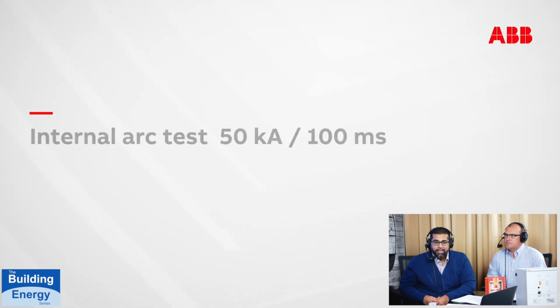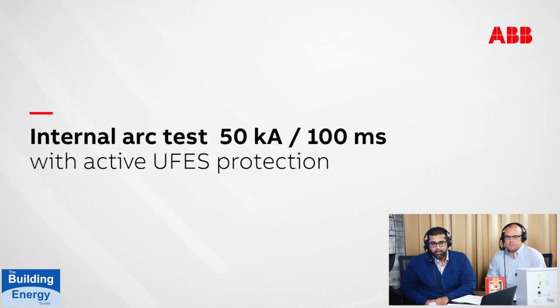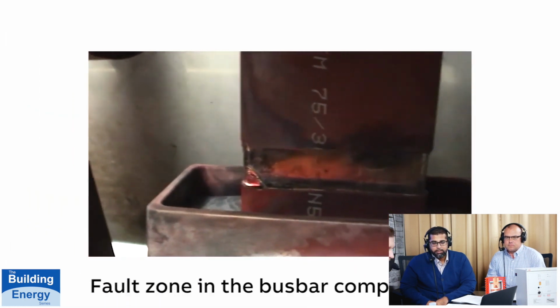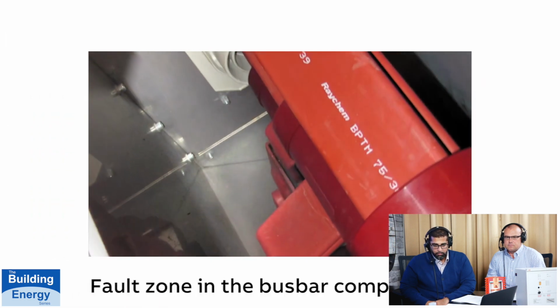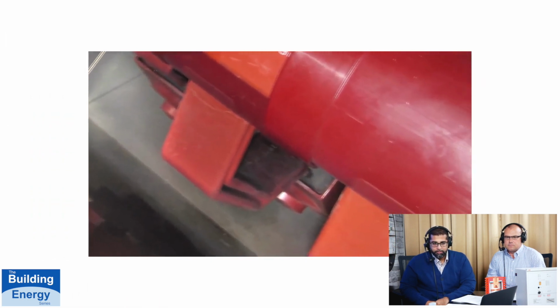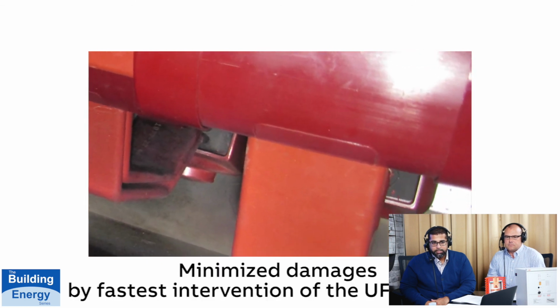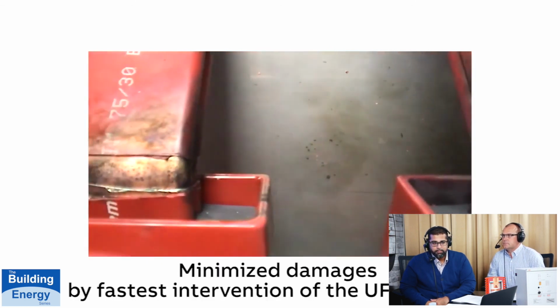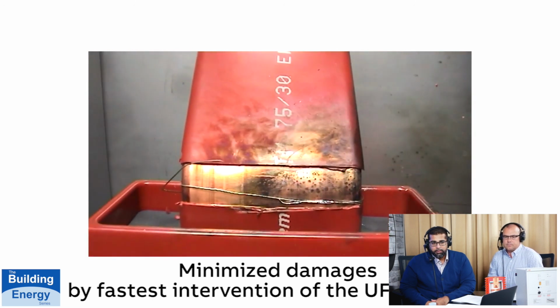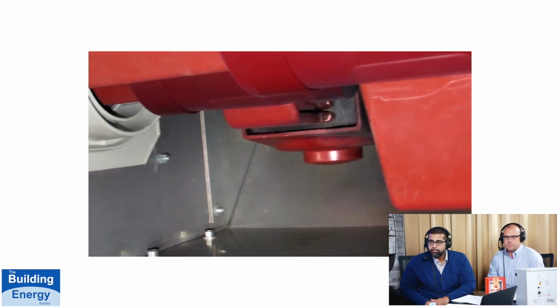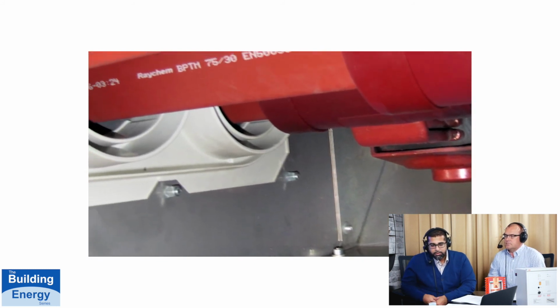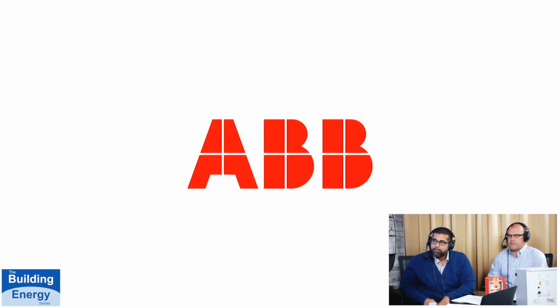And then this is a test with the UFES installed, where this will actuate in less than 4 milliseconds. You see the difference in the damage with the UFES and without the UFES that you saw previously. It's a minimal amount of damage. You still see some carbon buildup there, but it requires maybe some minor refurbishment. A lot of this depends on how severe the fault is as well. This is the worst case that we're simulating here, a three-phase fault. But with the UFES device, you've actually saved your switchgear.